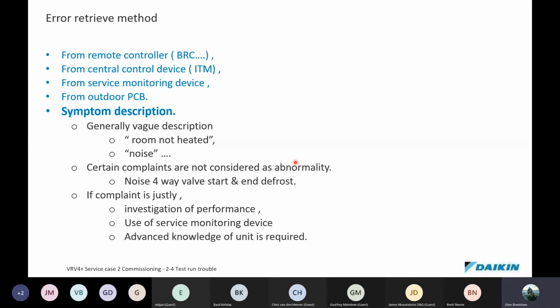Symptom descriptions are basically the type of descriptions that you get from a call from an end user. Room not heating, the room aircon's noisy. Certain complaints are not considered as an abnormality. Remember that when a unit changes from heating to cooling, there will be a shushing noise as the gas changes through the four-way valve. There's nothing you can do about it. You also get that at the end of a defrost cycle. So keep those things in mind. You also need to be able to explain that type of thing to an end user as it's part of the system's operation. If the complaint is justifiable, then investigation of performance would be required, and you might need to use a service monitoring device, and advanced knowledge of the unit is also required.